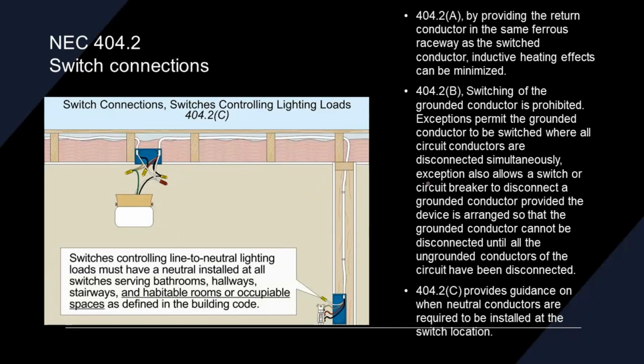404.2a, by providing the return conductor in the same ferrous raceway as the switch conductor, inductive heating effects can be minimized. 404.2, switching of grounded conductor is prohibited. So the grounded conductor, you cannot switch a neutral. No California three-ways, no Milwaukee three-ways.